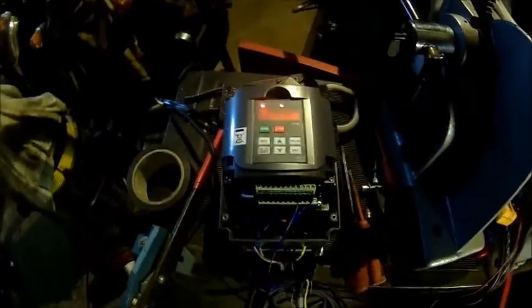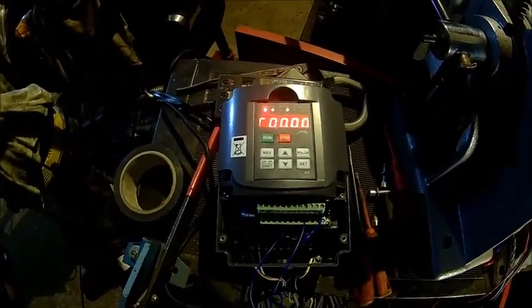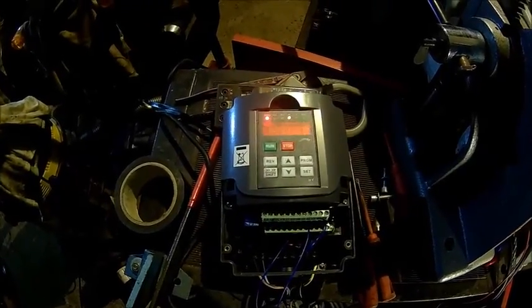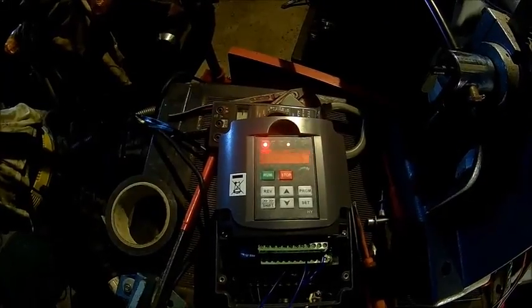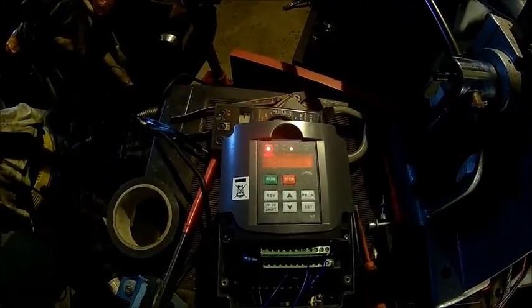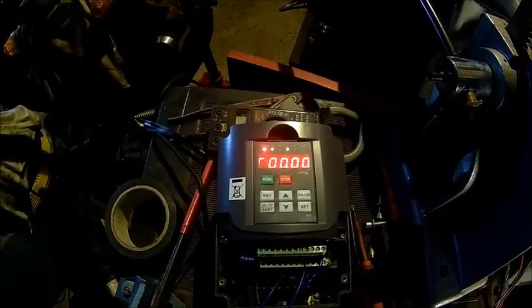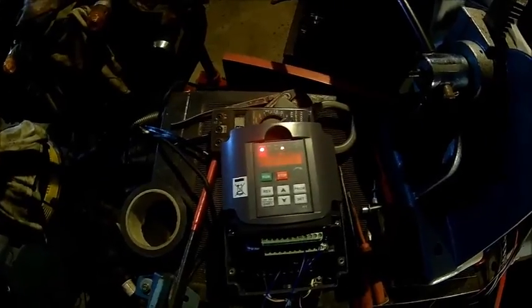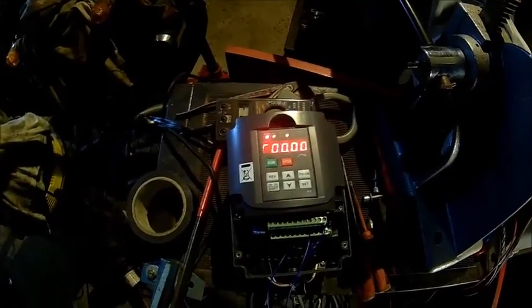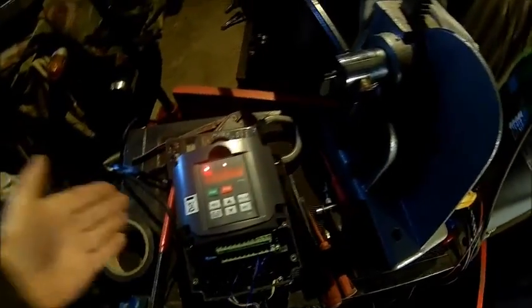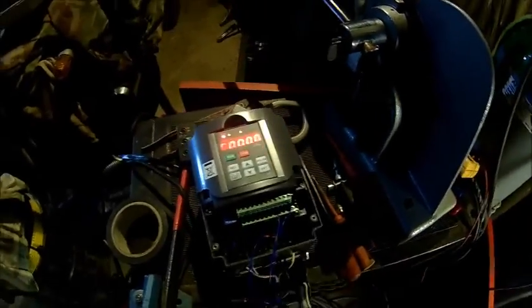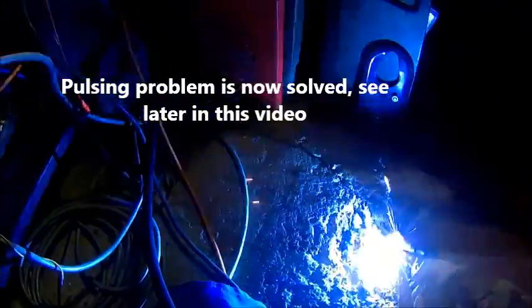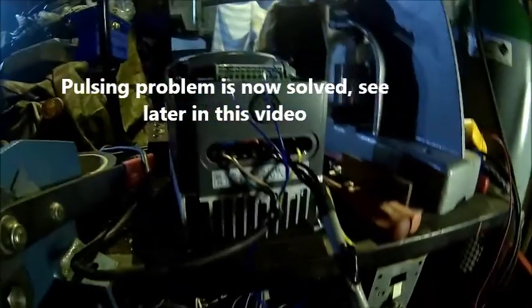That pulsing is two issues. One is the wire feed, and the other one is I need to change a few parameters on the inverter. I set the maximum frequency to 53 Hz, which is about right for that welder, because it's a 220 volt welder. 220/380. We have 230 volts, usually a little bit more, and so that's about right. The drive does well, it doesn't get hot. We are doing much better. We're now on position 4, whereas before, to get a reasonable weld with that feed, and yeah, that pulsing is actually the inverter, so we're going to sort that out.